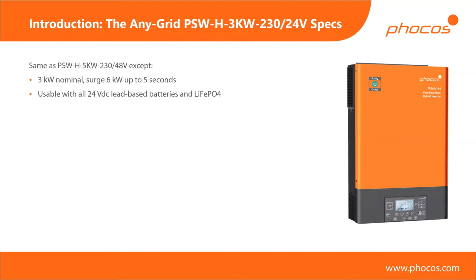So next to this flagship device, we have a smaller brother or sister, which has 3 kilowatts as a power output rating. It's also a 230 volt AC device, and it's designed for operating with 24 volt batteries. So we have half the battery voltage and a little bit more than half of the AC output power. All of the other features you've just seen or heard of, and that I'll explain later on, are identical between these two models. I know that there's a lot of people signed on from the Americas, so a lot of you will have 120 volts as a grid voltage. So for you, you'll have to wait a couple more months. At SPI we'll present it, and towards the end of the year, we'll be bringing out 120 volt variants of these units as well for your markets.